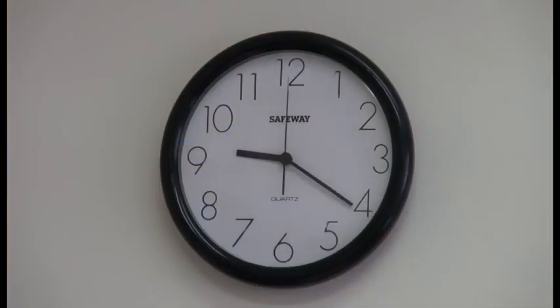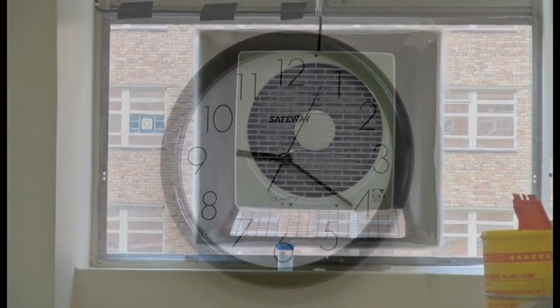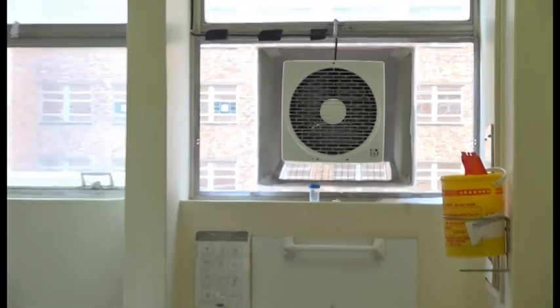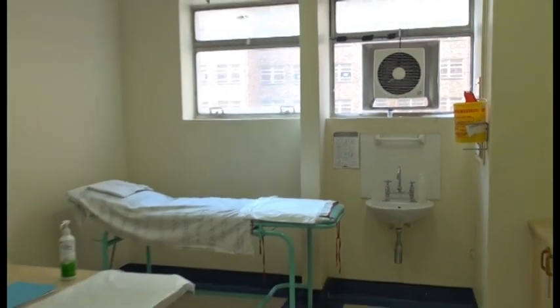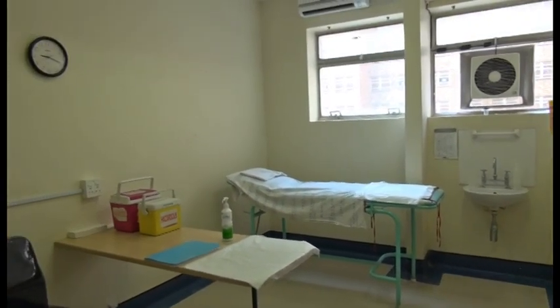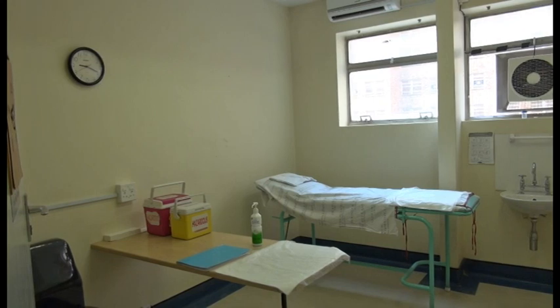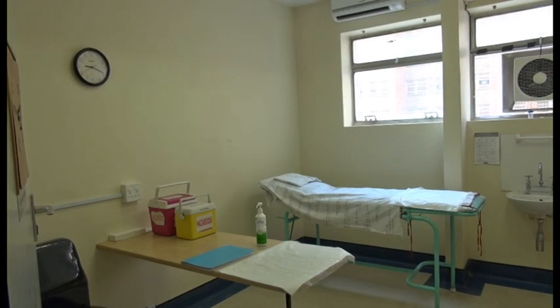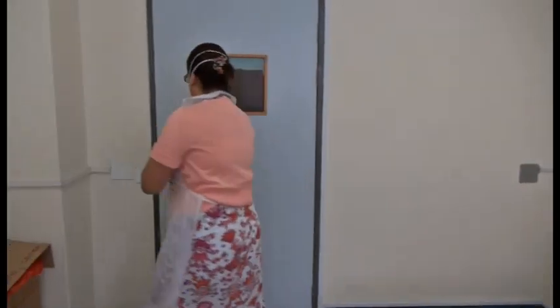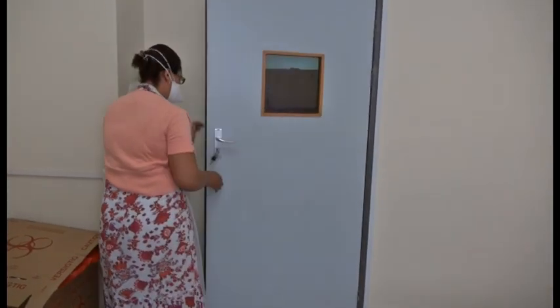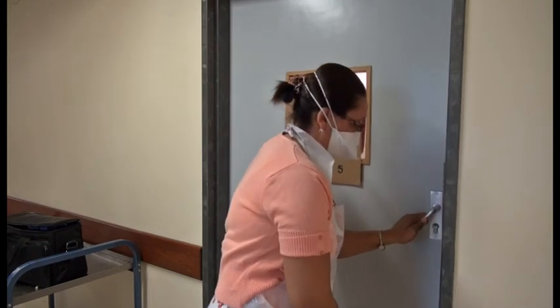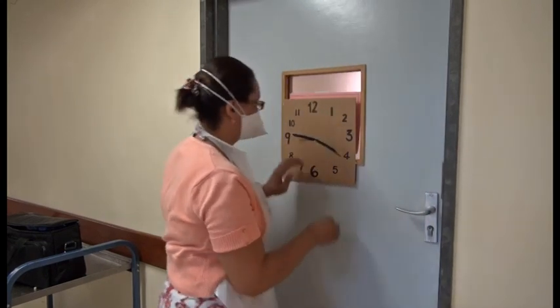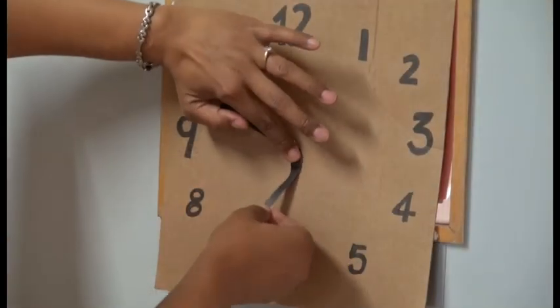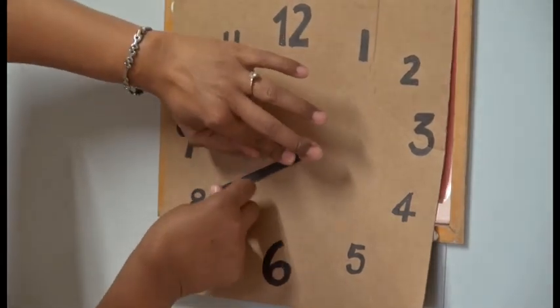The room. A minimum of 20 minutes should elapse between patients brought into the room for procedures if extracting air at 12 air exchanges per hour. If using a well-ventilated room, allow 30 to 40 minutes between procedures. Wait at least 10 minutes before exiting the room. Close the door immediately. Indicate the time when the next procedure can be done on the fake clock on the door.